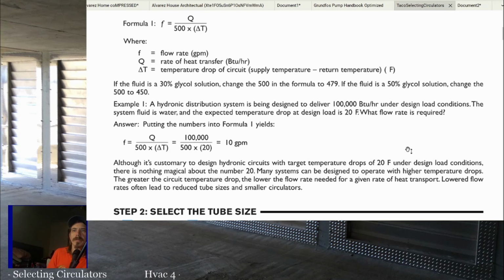So although it's customary to design hydronic circuits with target temperature drops of 20 under design load conditions, there's nothing magical about the number 20. Many systems can be designed to operate with higher temperature drops. The greater the circuit temperature drop, the lower the flow rate needed for a given rate of heat transport. Lower flow rates often lead to reduced tube sizes and smaller circulators.